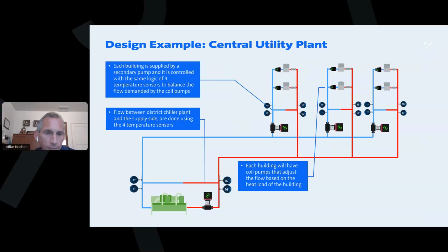Okay, here's another one. If you have a primary secondary system, you don't need to change the primary pump size. I would assume that stays the same, right? Yeah, often we don't need to change them. We had a case story in Singapore where they didn't have enough budget to do the primary side and the secondary side. So we did all the air handlers, we did all the secondary pumps, and we used the VFDs on the primary pump skid to slow that primary pump skid down, because remember, that primary pump skid doesn't need to produce the same, it can produce a little less head now.